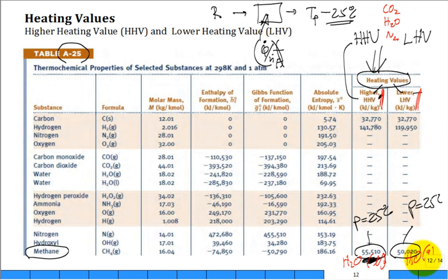They want that exhaust to go out so cold, 25 C, like the air temperature inside your house, that a lot of that water condenses and then it just is back into the home. You're not sending a pile of water vapor out. Try to keep it inside the home. I know it's going to be liquid, but then it's going to go back into the gaseous state inside your home. So you can look it up. Look up condensing furnaces. What they're trying to do is get not 50,000, they're trying to get 55,000.